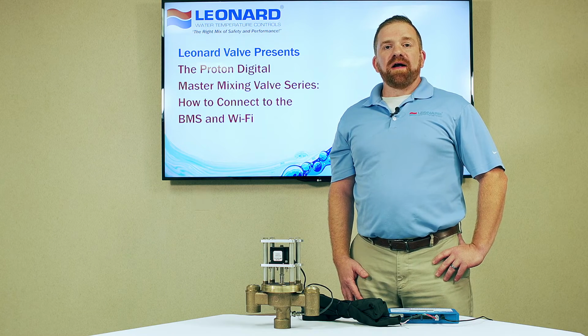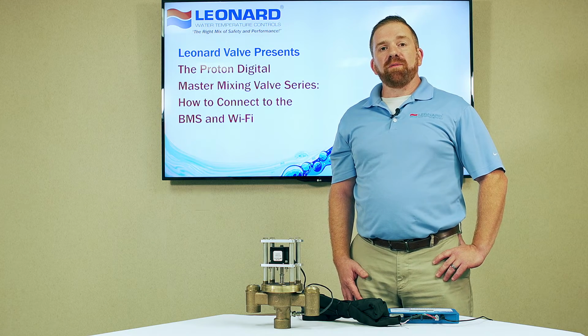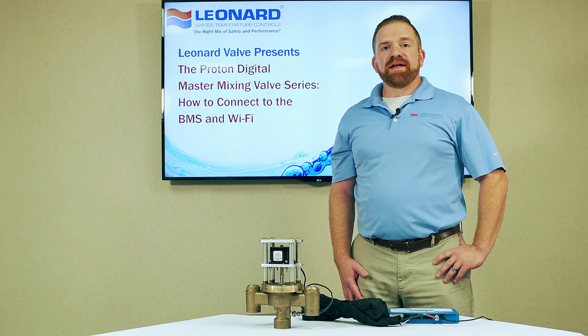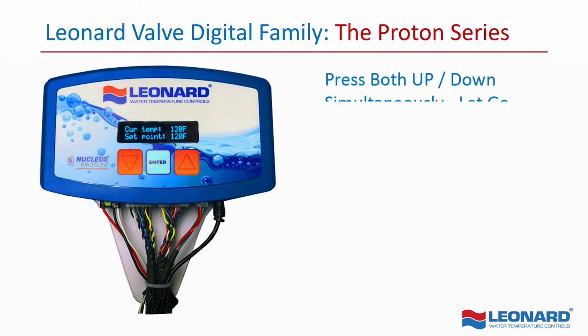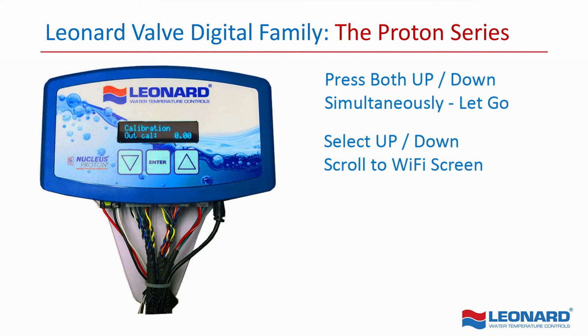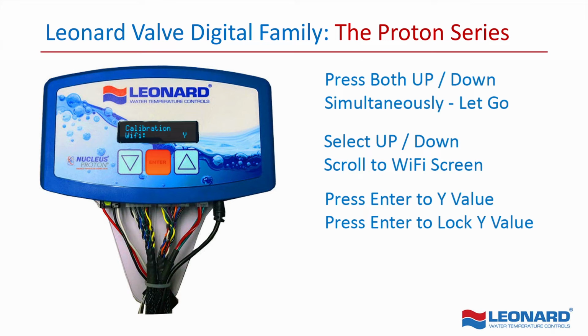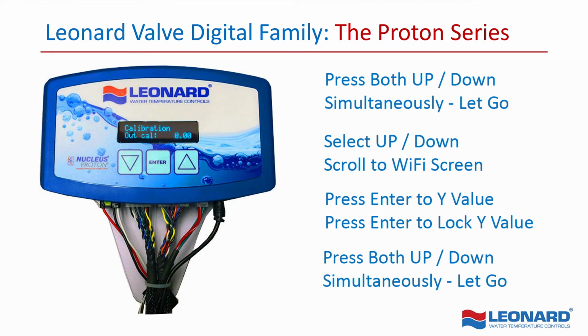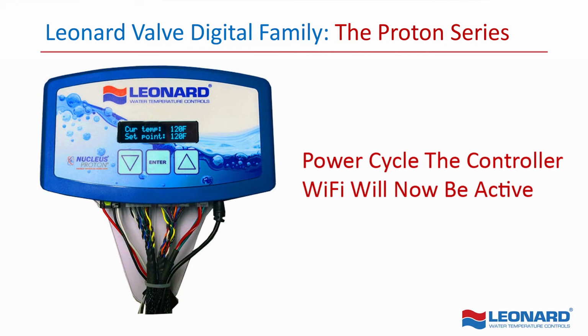First, you want to activate the Wi-Fi signal from inside of the Proton 3.0 box. To do this, you need to get into the calibration mode. Press the up and down arrows simultaneously and let go. Once you're in the calibration mode, use the up or down arrows to scroll to the Wi-Fi screen. Press Enter to change the value from N to Y. Press Enter again to lock in the Y value, and then press the up and down arrows again simultaneously to go back to your home screen. Finally, do a power cycle on your controller. Once the power is back on, Wi-Fi signal should now be activated.